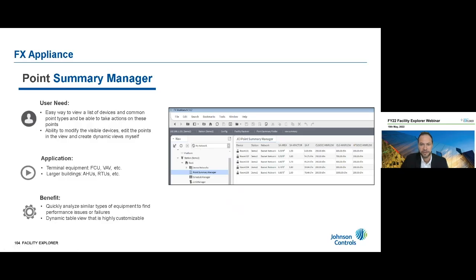Next is the Point Summary Manager, which helps building operators arrange a list of equipment devices by common point type so they can view them in a dynamic table and take action on those points. In other words, it helps develop a template of points in a table, making it easy to view and compare data from similar types of equipment. For example, with VAV info like zone temperature across different VAVs or zones in a building, you can list all the zone temperatures and spot any potential issues. This becomes very beneficial with a large number of typical equipment, like fan coil units or VAVs, since having that single table view allows you to troubleshoot issues easily.